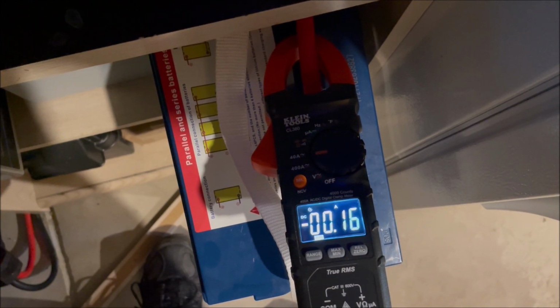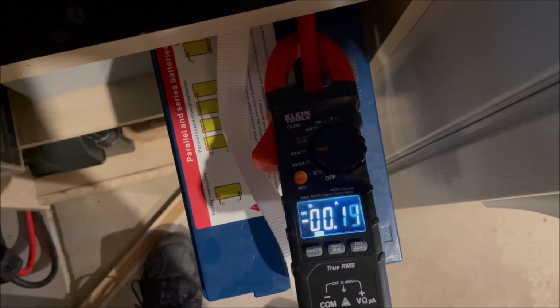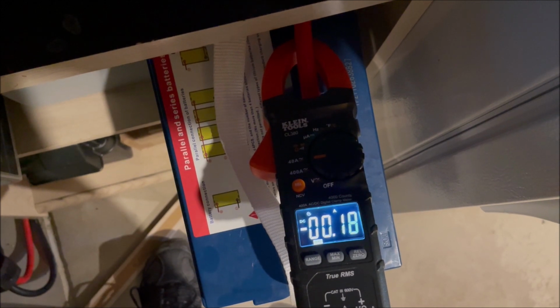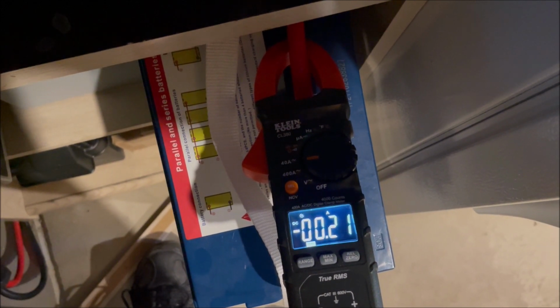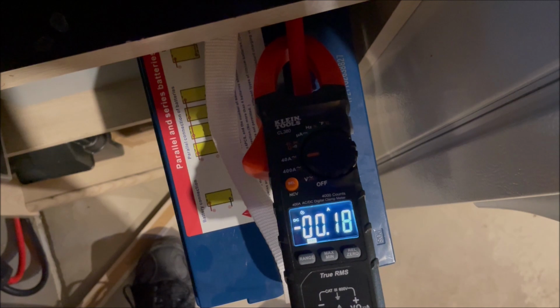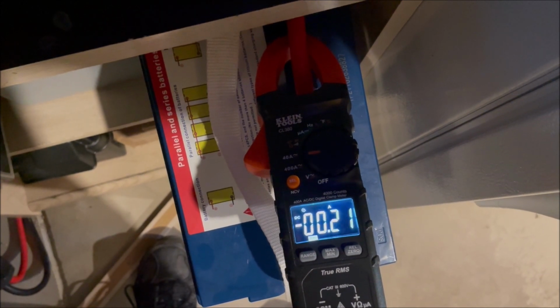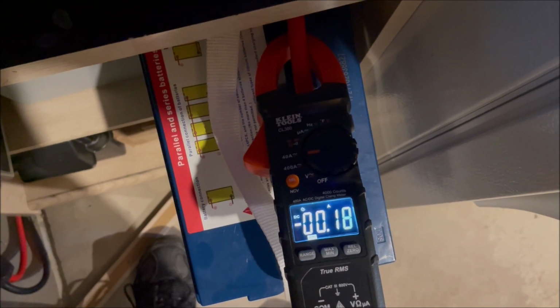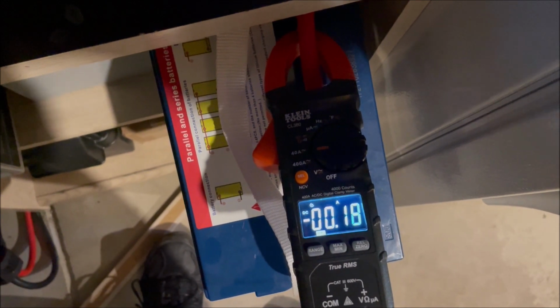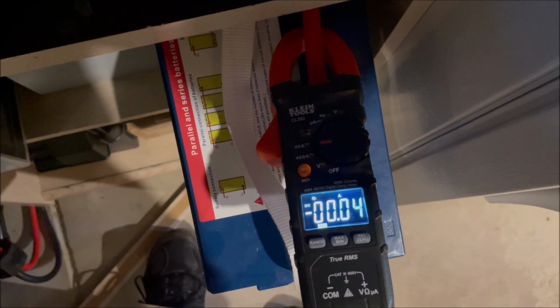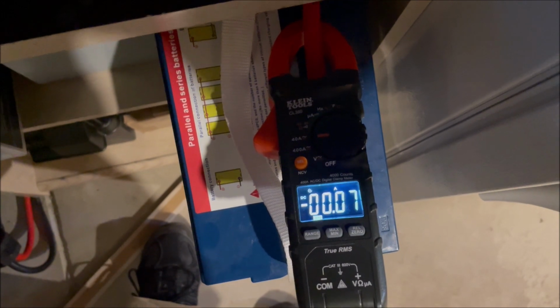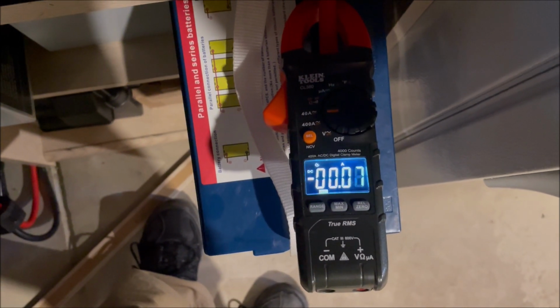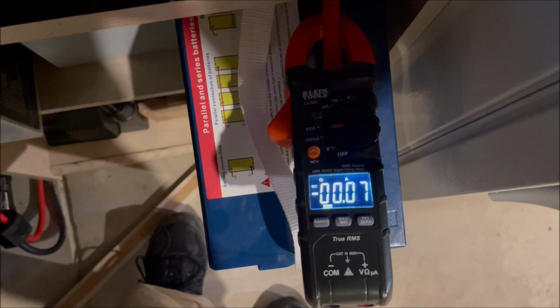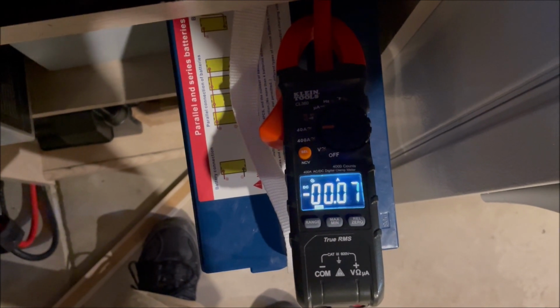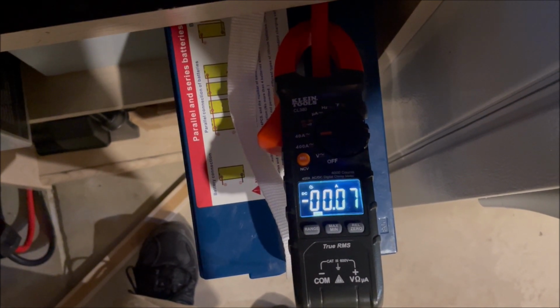All right, so you see that? So it's now helping to power the inverter, which is pulling about 0.8 amps. Okay, now if I turn the inverter off, we'll see that current draw in that battery go back down to pretty much nothing. So yeah, we see that this is still part of the bank. It hasn't cut out. So we're good to go at our voltage setting in the charger for 13.7 volts.